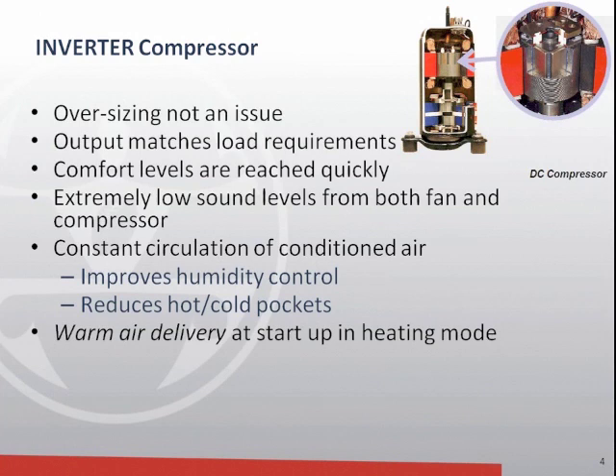The comfort levels are reached quickly because in a high temperature condition where your space has warmed up and you need to get it down to conditions very quickly, the inverter actually can produce more than the nominal capacity of the system. So if, for example, you had a 1-ton system installed in a room, a sunroom that's been off or unoccupied and maybe 85 degrees, the inverter, when it has a call for cooling, detects this condition. It'll actually ramp up to as much as 1.5 tons or 50% more than its nominal capacity and brings the temperature in the room down very quickly, and then cycles back and modulates itself to just the amount of cooling that's needed. You can think of it as hitting a big hill when you're driving with your cruise control on. The car is going to throttle up to its maximum capability till you get to the top of the hill, and then as you level off, it's going to back the throttle down.